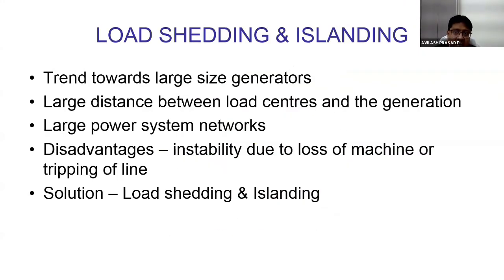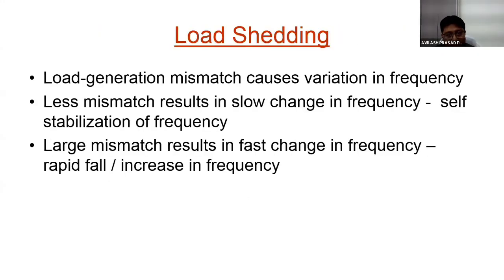Now coming to the load shedding and islanding of the captive power plant, which I have shown. It is necessary because there is a trend towards large size generators, a large distance between the load centers and generation, and large power system networks, because of which there is instability due to loss of machine and tripping of line. So the solution is load shedding and islanding. Load generation mismatch causes variation in frequency. A small mismatch results in a slow change in frequency and will result in self-stabilization of frequency. A large mismatch results in a fast change in frequency, a rapid fall or increase of frequency.